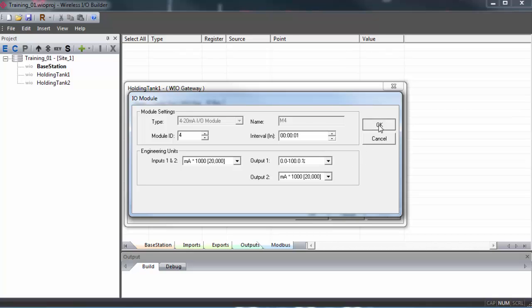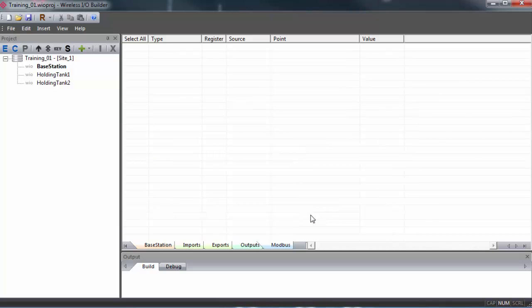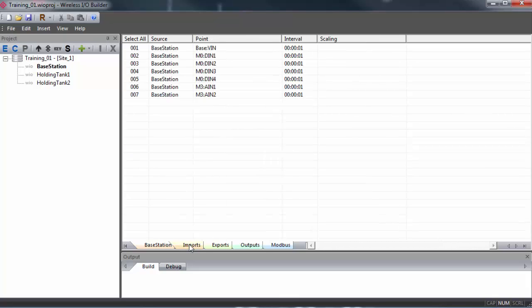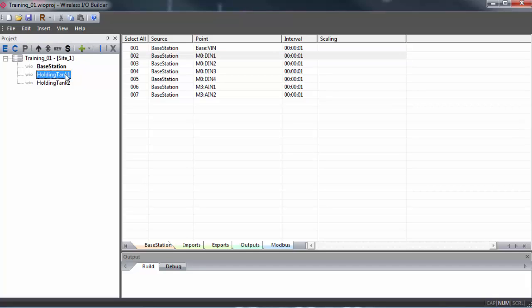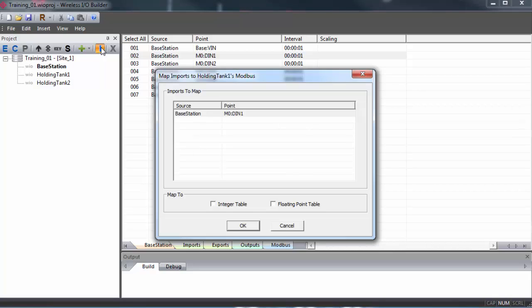Again, making sure the module ID is correct. And here I'll set the output one to zero to 100%. Now we can map our data. What we would like to do is pass our input one from our base station to the outputs of holding tank one and holding tank two. To do that, all we have to do is double click on base station and then click on the imports tab, then select M0 digital input one. The M0 refers to module zero. Click once on holding tank one, then click on the import button in the toolbar. This will bring input one from our base station as a source into our holding tank one.